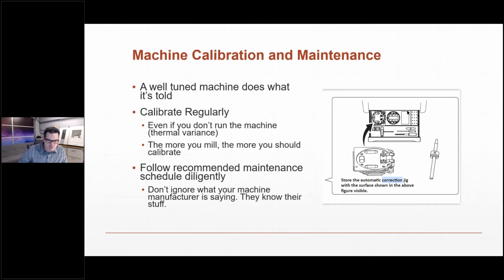Now, the reason calibration is necessary on a lot of machines is we get a couple of things happening in the lab. First, there's a thermal variance. As the ambient temperature in the laboratory goes back and forth, the machine can grow and shrink. That's a dimensional change that's very small, but not insignificant, when we're talking about trying to achieve micron accuracy with some of these machines.